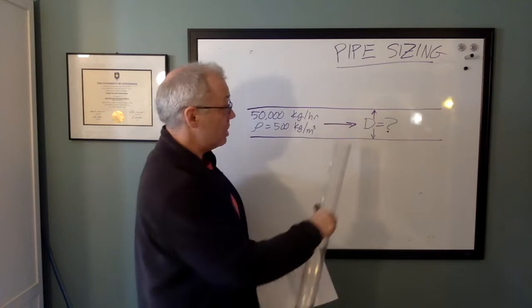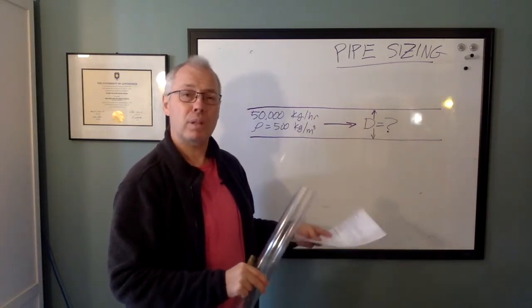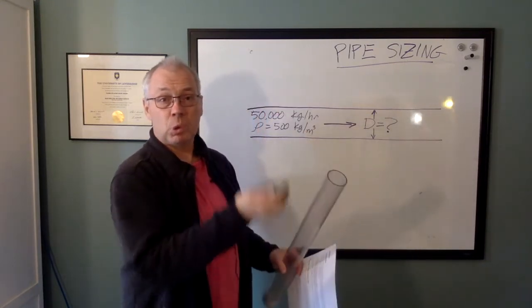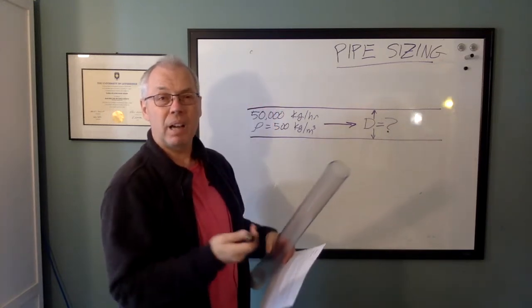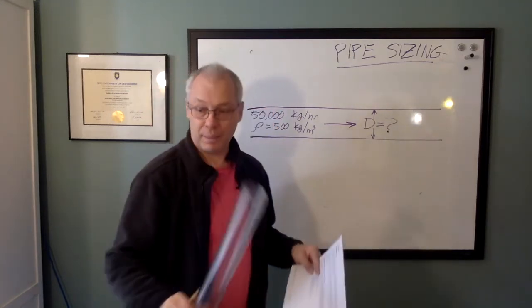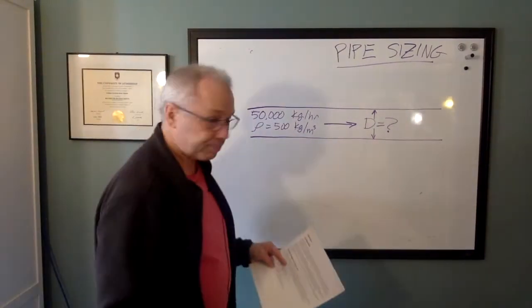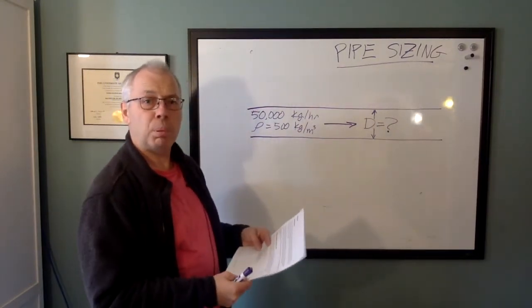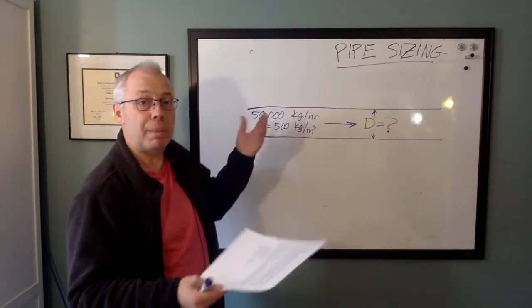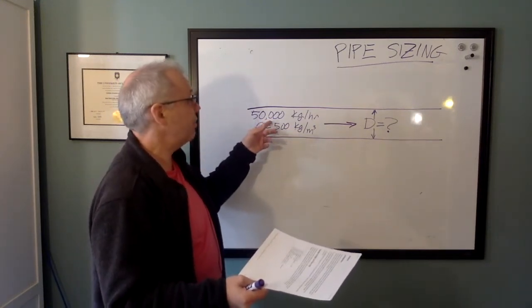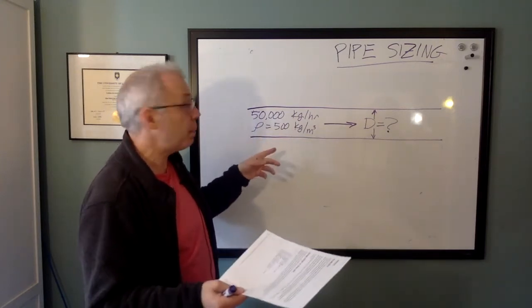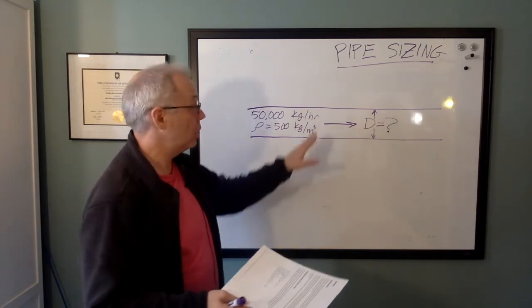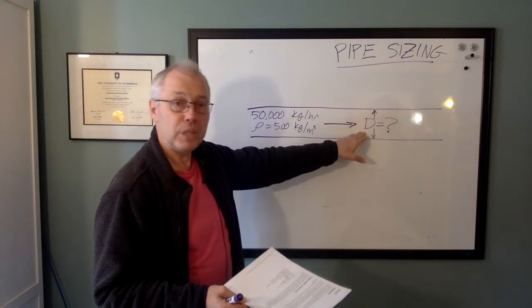So the question of the day is, what size diameter do you need your pipe to be? Do you need a two-inch line or a three-quarter inch line? How do you calculate it? That's what we're going to look at. We're going to look at this with an example. The example we're going to pick is 50,000 kilograms an hour of liquid propane. Propane has a density of 500 kilograms per cubic meter, and we want to decide what inside diameter is needed for this pipe.